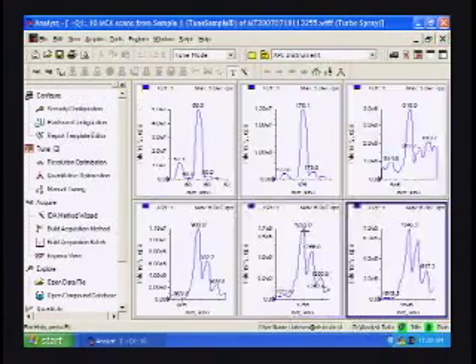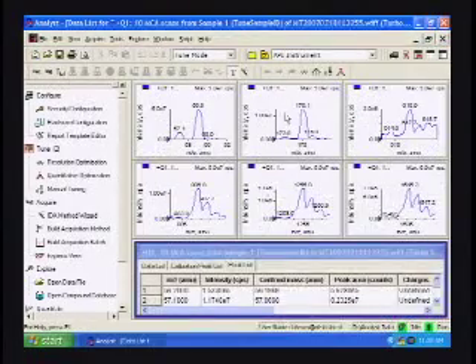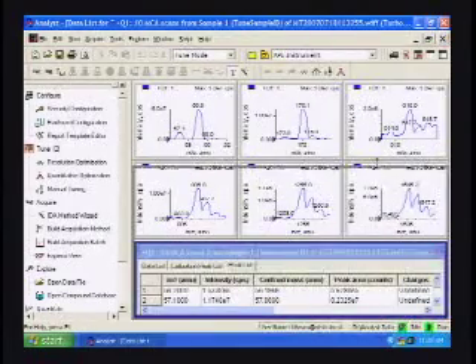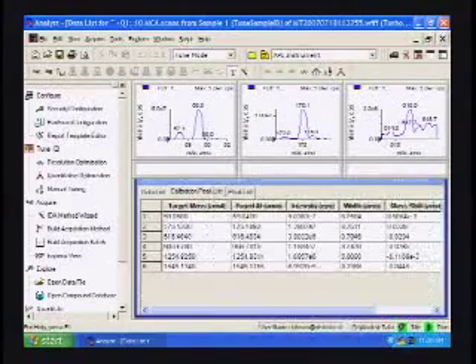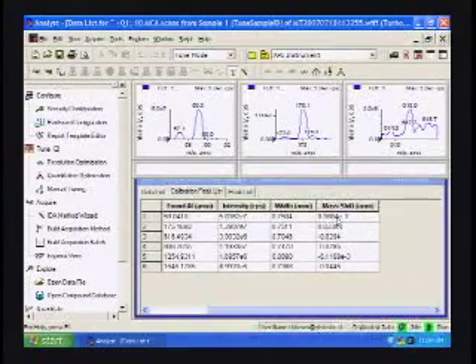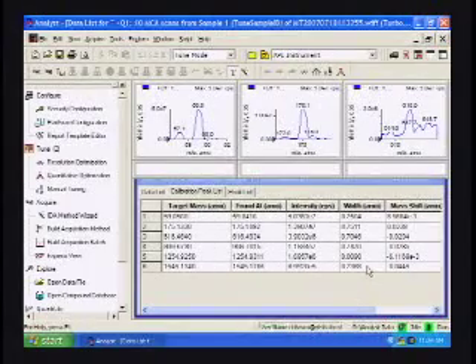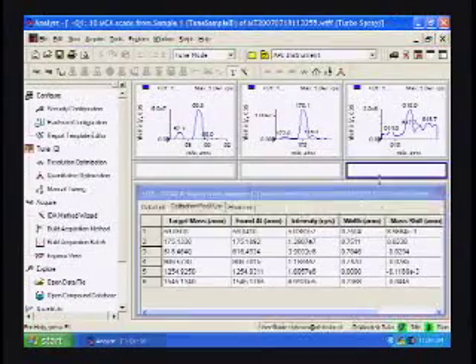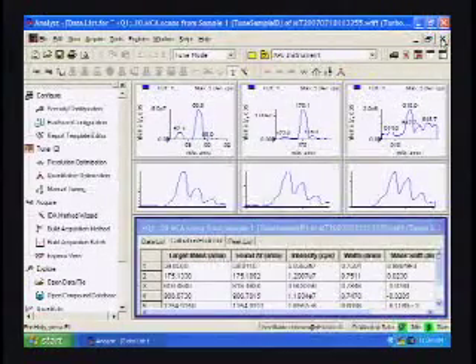We'll right click again, open file, right click again, list data, and let's take a look at the chart again. I'll click on calibration peak list. So the mass shifts here are all within 0.2 or less. The widths, again, this ion failed. So this does not change the calibration tables whatsoever. All we're doing here is merely checking the calibration of the instrument. So as far as I'm concerned here, Q1 has failed.